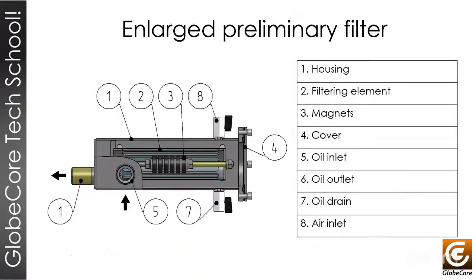Also, we have a really huge preliminary filter. This preliminary filter is redesigned for Globecore to reduce the resistance that this filter generates to the vacuum system. That's why we have a really big, in my words, maybe a huge inlet filter, and this filter will reduce the resistance for the oil getting inside the machine. Also, we will find some magnets in this filter. These magnets will help you remove metal particles in the oil, and that will help you reduce problems with the oil. You can see it's a really easy configuration for cleaning this filter.